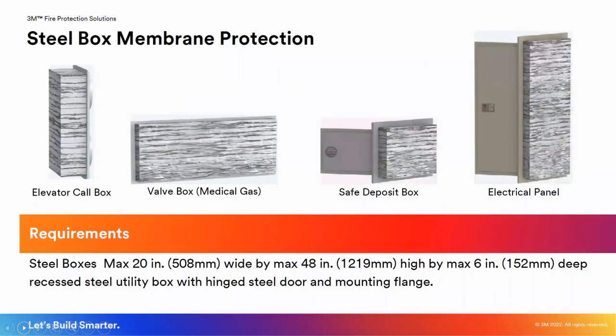It can also be used for membrane penetration. So if you had an electrical panel or an elevator call box, for example, that was within a fire-rated wall assembly, you could use the EMAT to protect the backside of the box or the electrical panel. You would simply use one of our 3M spray adhesives, sprayed on the backside of that panel or that call box, and attach the EMAT material that way. Any gaps and cracks would be taped off with one of our appropriate foil tapes. Next slide, please.